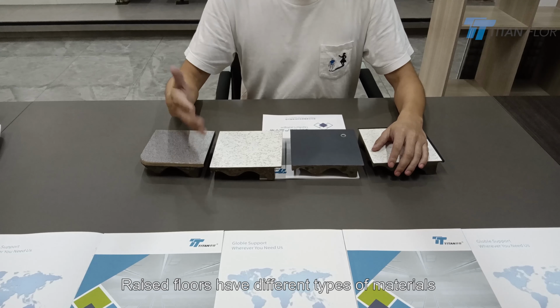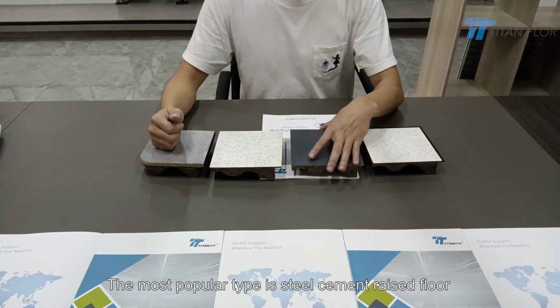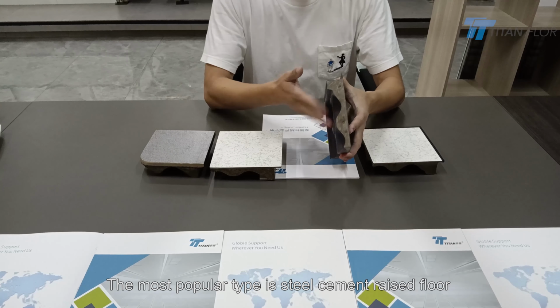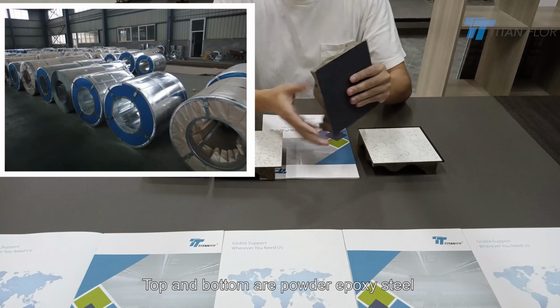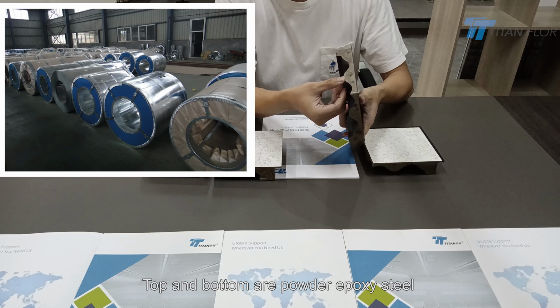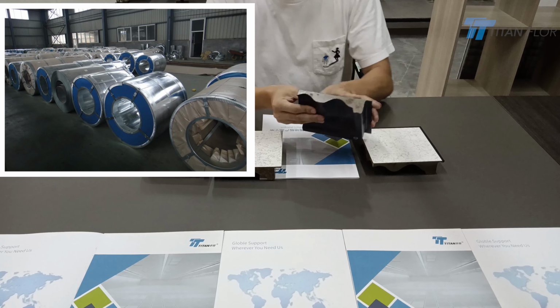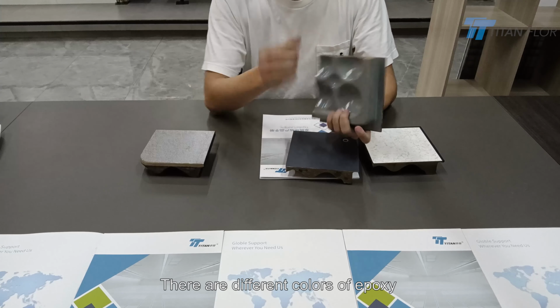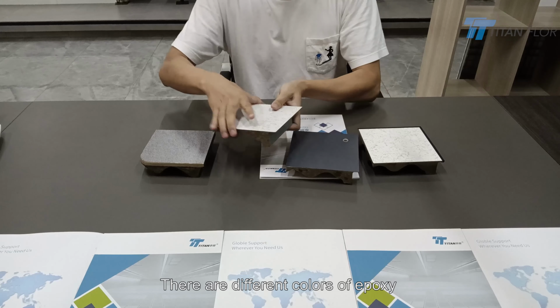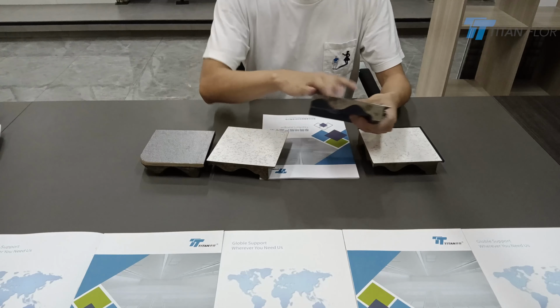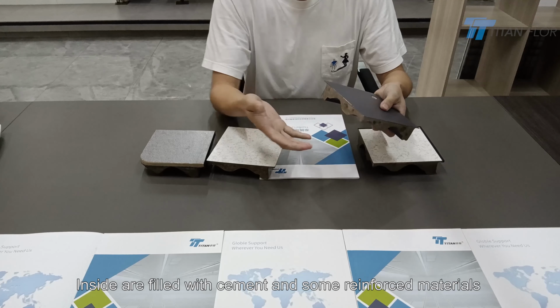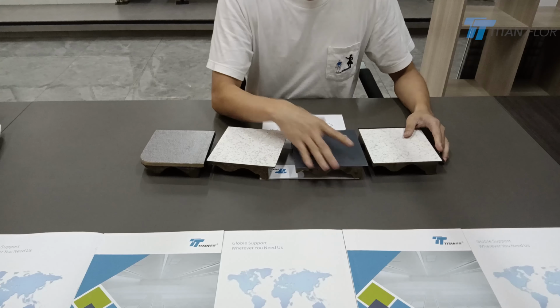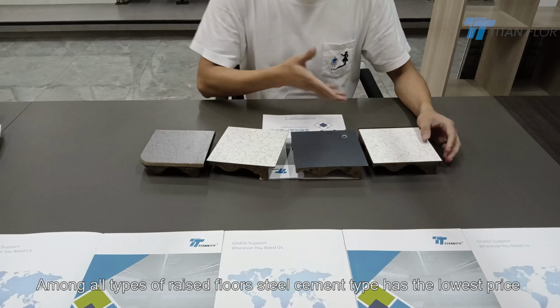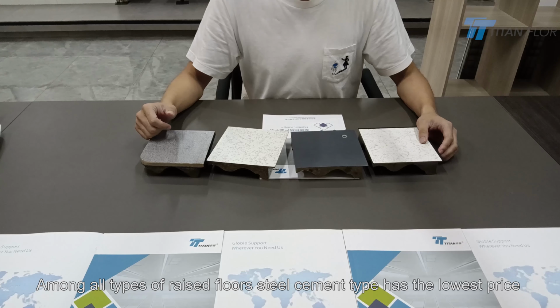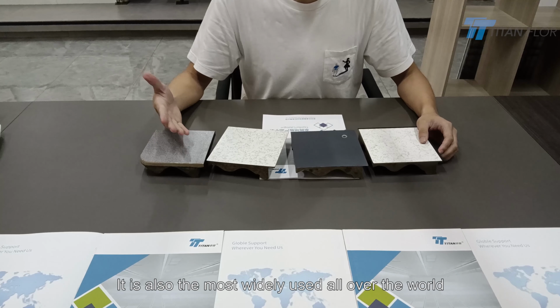Raised floors have different types of materials. The most popular type is steel cement raised floor. Top and bottom are powder epoxy steel. There are different colors of epoxy, and inside are filled with cement and some reinforced materials. Among all types of raised floors, steel cement type has the lowest price. It is also the most widely used all over the world.